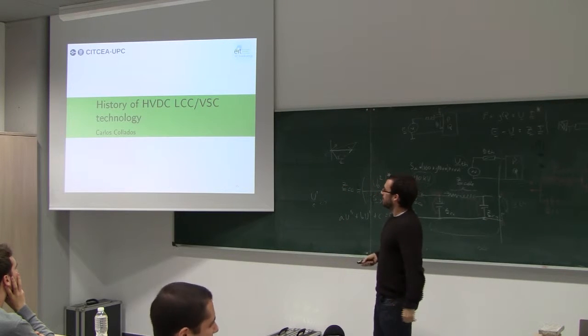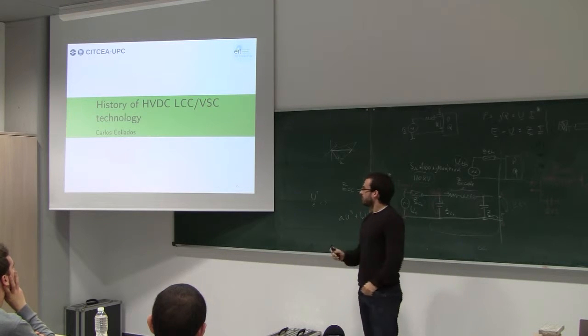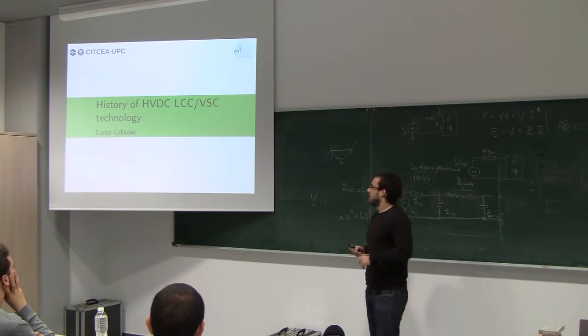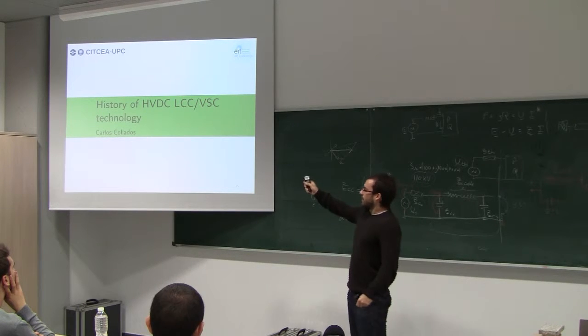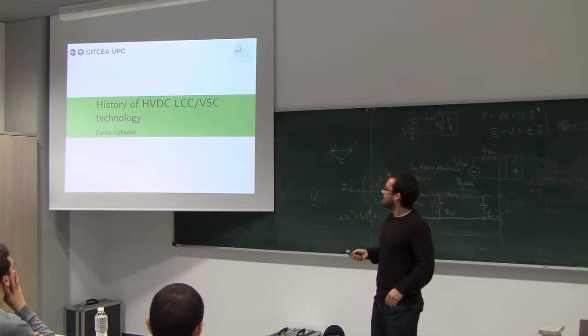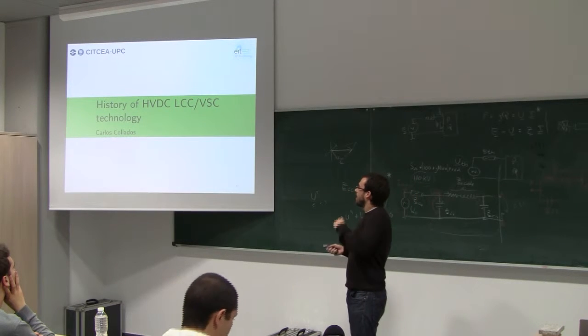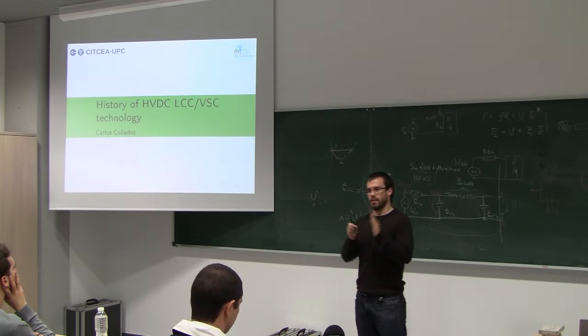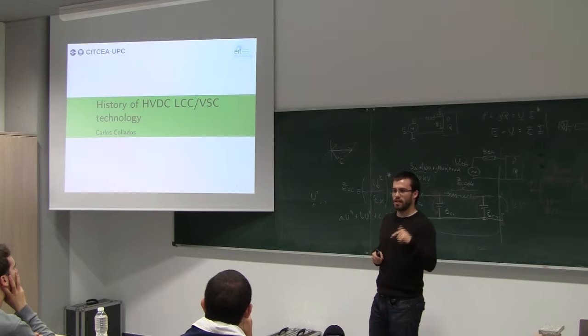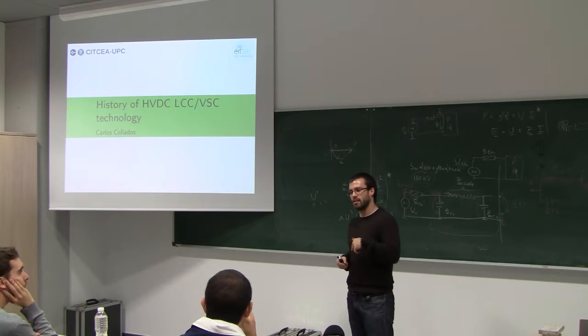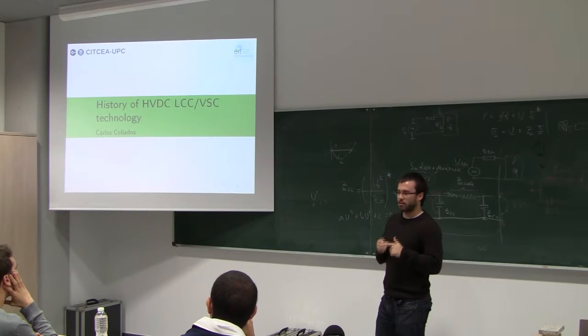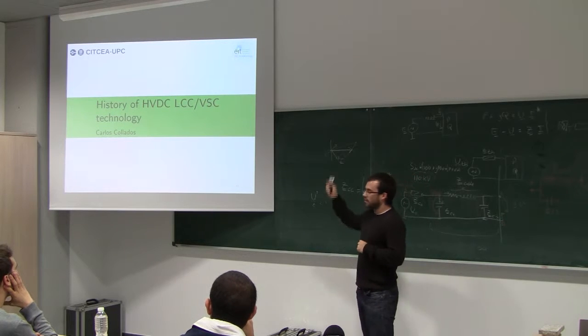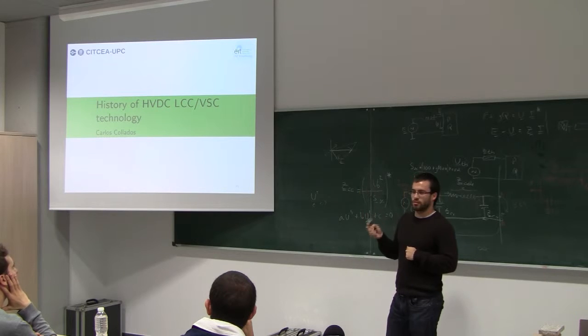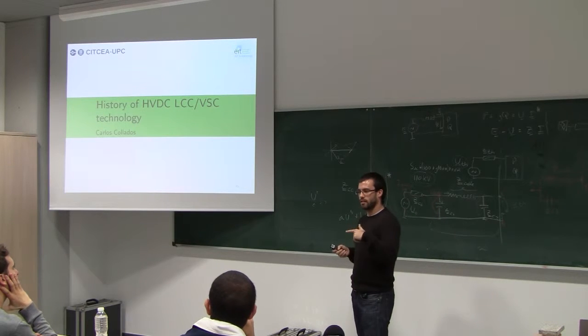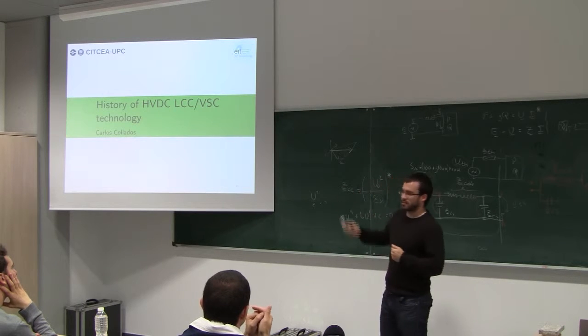As you see here, there are two technologies, LCC and VSC converters. LCC is line commutated converter, and they work with thyristors. With a thyristor, you can control when it turns on, but the turn off is synchronized with the current of the grid, so when the current of the grid goes to zero, they turn off. So you only can control when they turn on. VSC works with IGBTs, so you can control when they turn on and when they turn off. So the flexibility of VSC converters is higher.